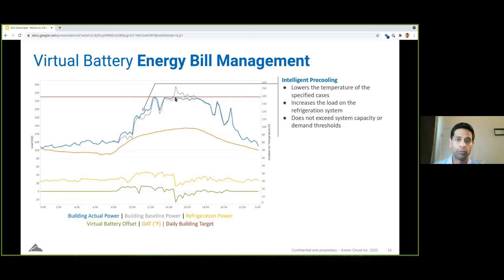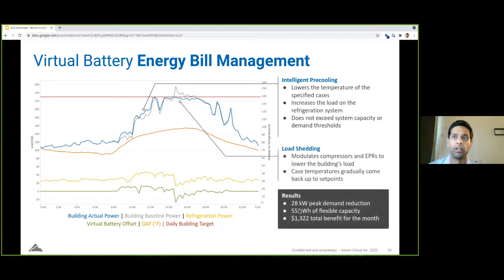So that pre-cool that we were able to accumulate in the beginning of the day allows those cases to float back up in temperature. And we do not let those go back past their set points or past any food safety threshold. So in doing so, we're basically using that stored charge to curtail that load. In this particular case, this store achieved 28 kilowatts of peak demand for 2 hours, which essentially resulted in...